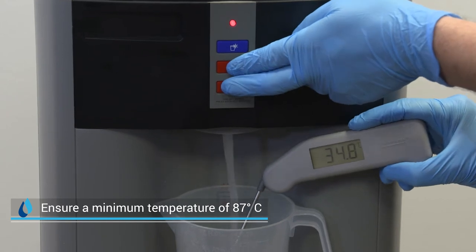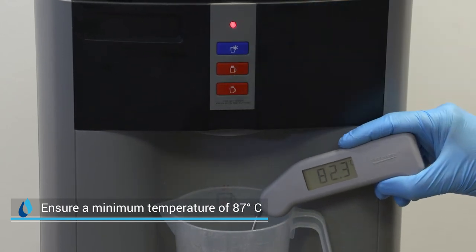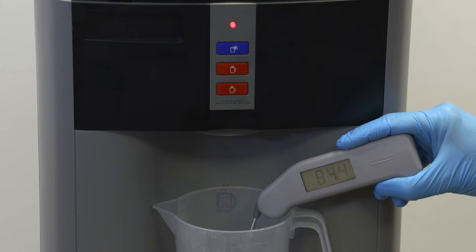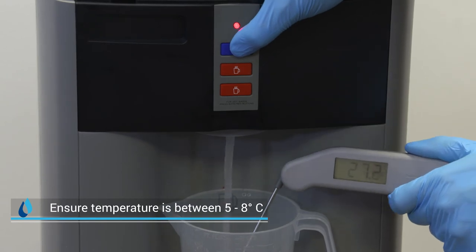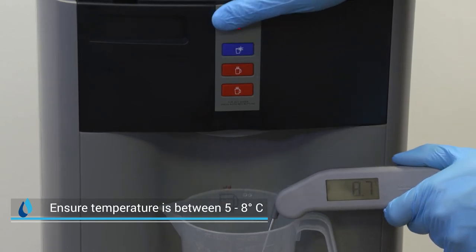To test the hot water temperature, use a thermometer to test the temperature. It should be approximately 87 degrees centigrade. Once the compressor has turned off, the cold water temperature is ready to be tested.